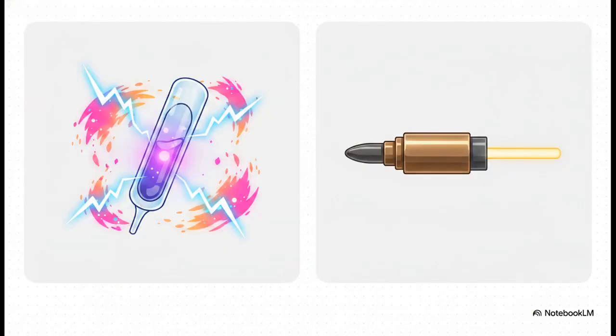A true pH measurement system actually requires two distinct halves. On one side, you have the glass measuring electrode, which responds dynamically to whatever your sample is. On the other side, you absolutely must have a reference electrode, which supplies a super stable, fixed voltage that is completely independent of the sample. The big takeaway here is that your pH meter doesn't just measure a single voltage. No, it measures the difference in voltage between these two electrodes.